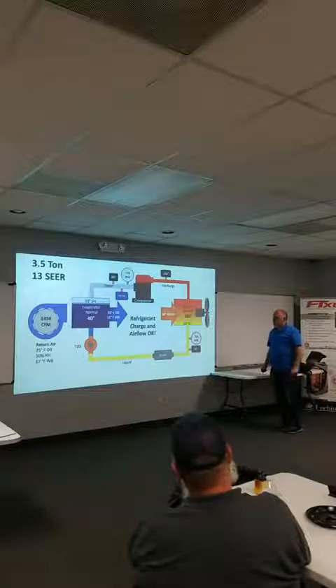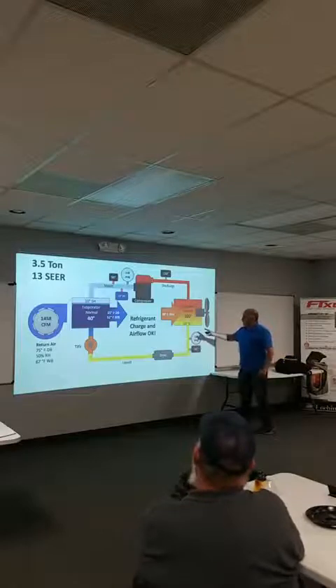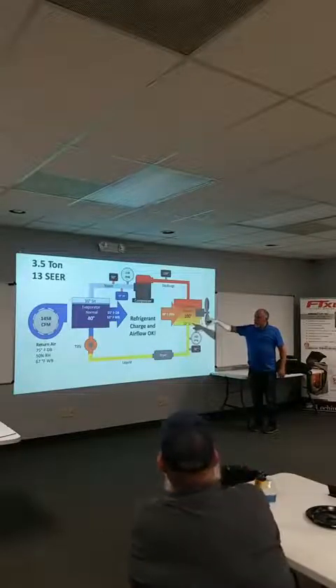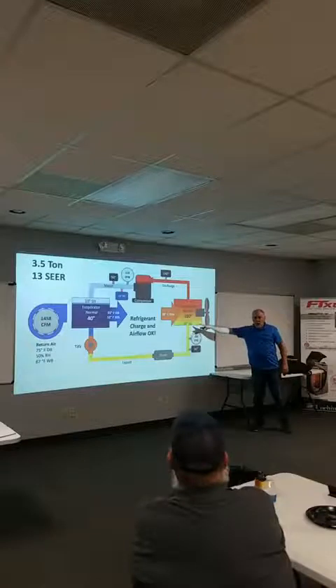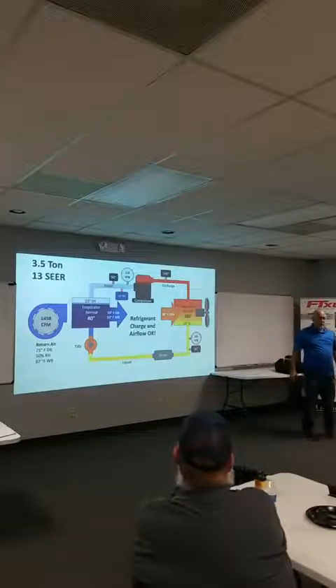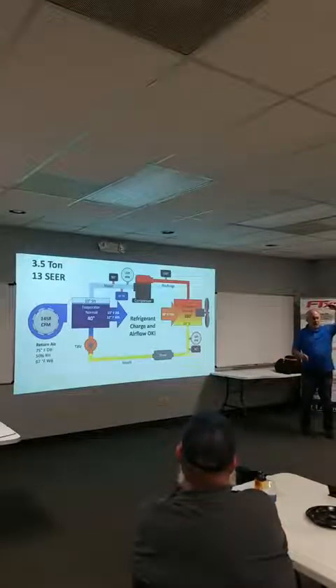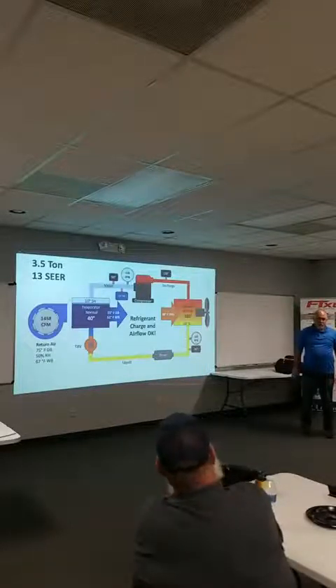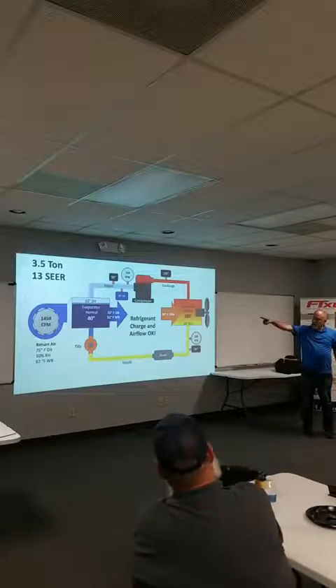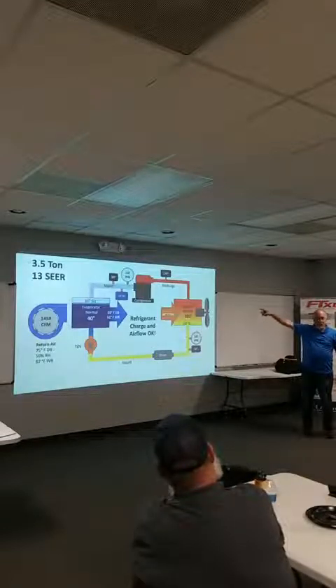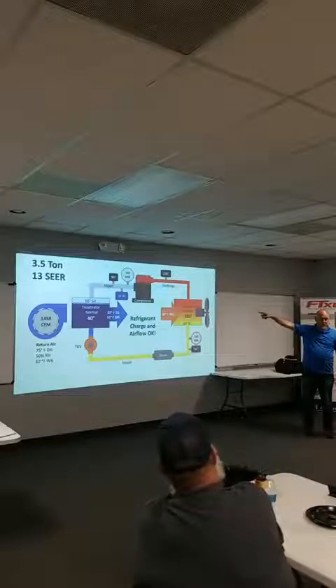So here's just a visual, and I got so screwed up with this when I was in school, but I want to make sure that we get this down tonight. When you're looking at a refrigeration system, there's just a liquid seal at the bottom of the condenser, right? I always got in my head that the condenser was full of liquid. If somebody told me the condenser's where the liquid's at, the evaporator's where the vapor's at, I'm like, okay, well, the evaporator is almost full to the top of liquid, and just the very top of it is a little bit of vapor. And all the vapor is in the condenser, it's actually raining in there. It's de-superheating, saturating, and subcooling to liquid, okay?